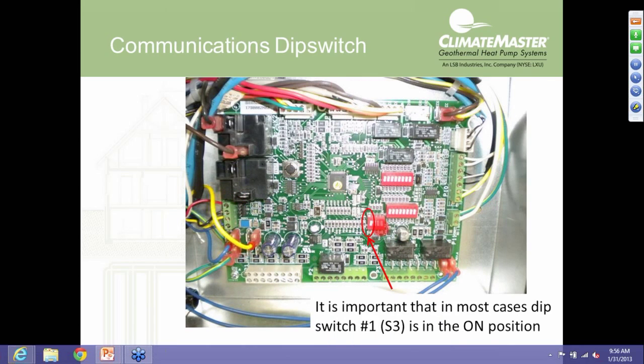Let's talk about these dip switches a little bit. Bank 3 is the smaller of the three dip switch banks. The very first dip switch, the one on the far left-hand side as you face this board, is dip switch number 1, and that should always be in the on position. That is so that we have communication to the communicating thermostat. If it's moved to the off position, your communicating thermostat will not communicate with the DXM2 board. So that must always be in the on position.